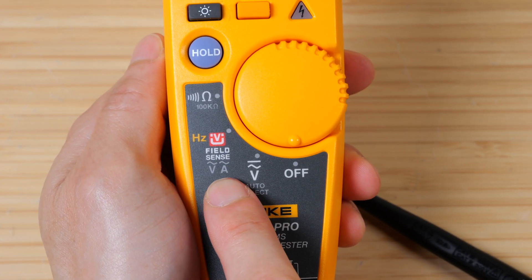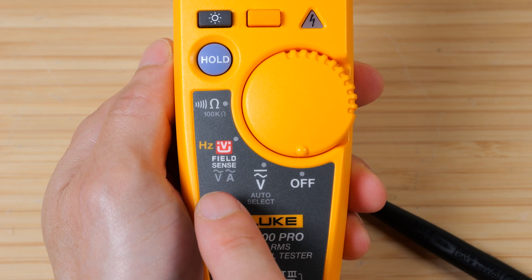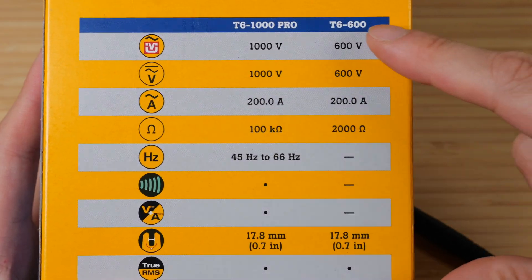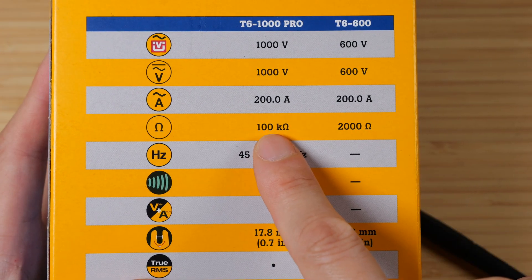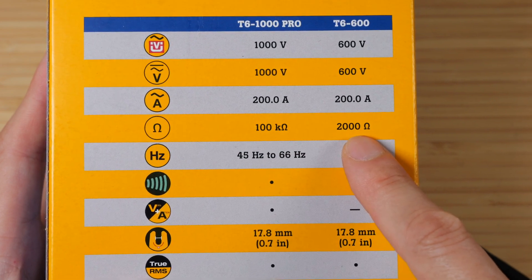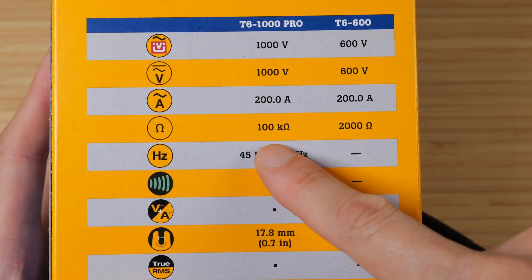Except it cannot do AC amperage. This is mainly for detecting AC and DC voltages, but only AC amperages. The T6-1000 can do 1000 volts and the T6-600 can do 600 volts. Both of them can do up to 200 AC amps. The Pro can measure resistance up to 100 kilo ohms. The T6-600 can only measure up to 2000 ohms. This specification is rather small compared to a regular digital multimeter.